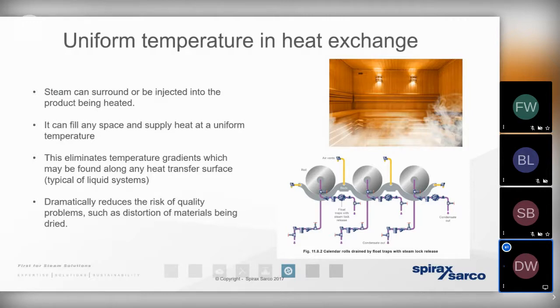So that uniform exchange of heat energy means that we're less susceptible to getting striations and cold spots in the heat exchanger if we're using steam compared to using water as the primary source of heat energy. That's yet another reason why we need smaller heat exchangers if we're using steam compared to water.